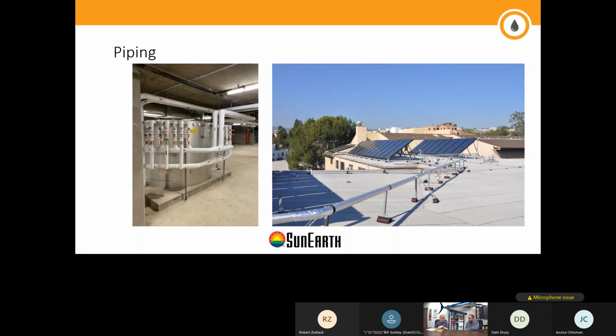So what they had them do, they made them put in a pressure balancing valve that, when there was a high demand, would open up and provide full flow to the building. That's the number one thing we don't want to do on that side of a system: compromise or impact the flow to the building, per the plumbing engineer, or the pressure to the building and fixtures. We do not want to compromise that.